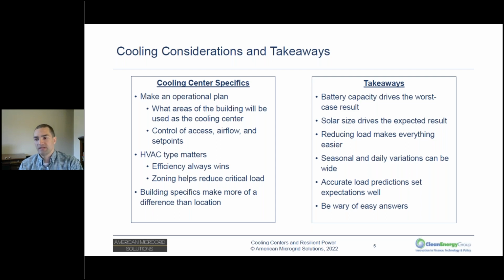I'll come back to the piece about manual or automatic load shedding. One part of your operational plan might be having a person walk around and turn things off. That's a cheaper way to shed load because it's less expensive than installing hardware that can automatically turn things off. It's also more flexible—if the sun is out and shining and everything is good, you can have more stuff turned on as long as you can keep the battery full at the end of the day.